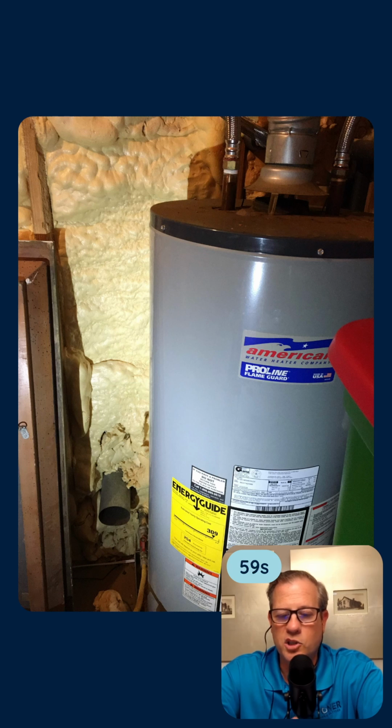Okay, so there's two things that we had a problem with here. Actually, three. The first one is this was an open cell foam enclosure. It was a retrofit. You can see some of the contents left on the left-hand side and the right-hand side of an attic. That is a water heater that's open combustion, 80% AFUE, annual fuel utilization efficiency. You cannot have an open combustion appliance inside a foam envelope.